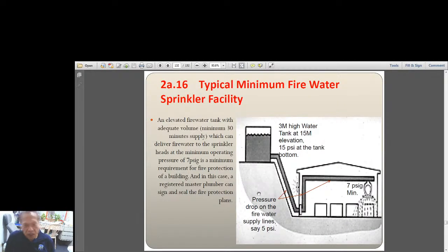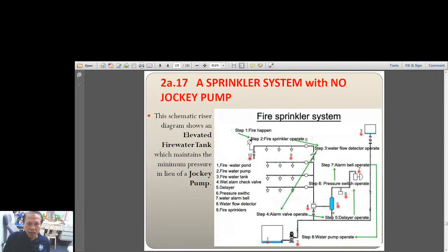And here is just an illustration. You can also have an elevated water tank that can supply fire water to your last sprinkler. Here, take note that in the drawing there is no fire pump. It's only the pressure of the tank that supplies the minimum pressure of 7 psi at the last or the farthest sprinkler. Okay. And here is another schematic showing there is no jockey pump. Here you have the fire water tank, and there is only one pump here.